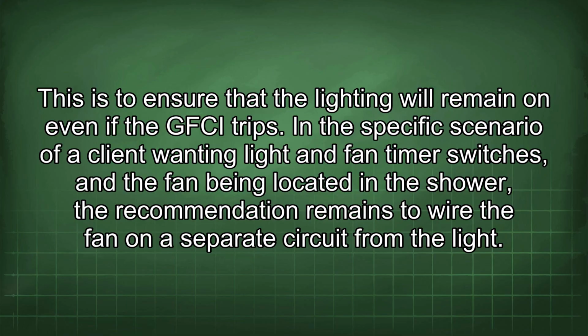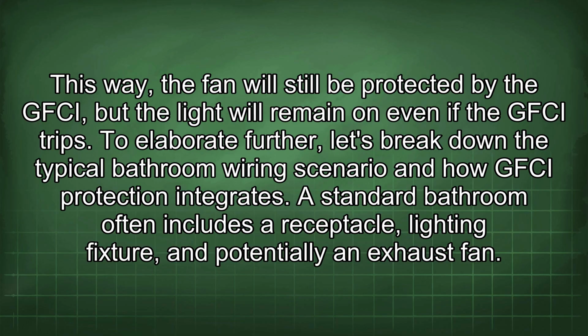In the specific scenario of a client wanting light and fan timer switches, and the fan being located in the shower, the recommendation remains to wire the fan on a separate circuit from the light. This way, the fan will still be protected by the GFCI, but the light will remain on even if the GFCI trips. To elaborate further, let's break down the typical bathroom wiring scenario and how GFCI protection integrates.